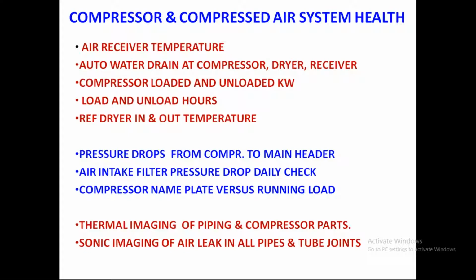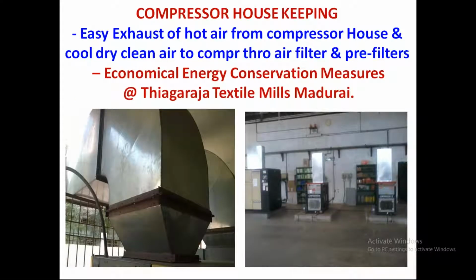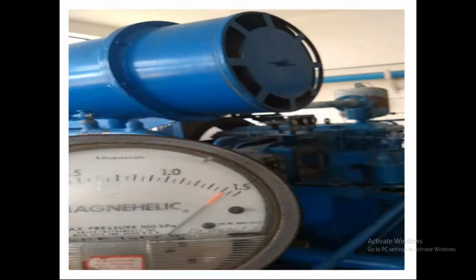What is the reason for heat rejection, as I was telling you before? 70% of the heat is rejected, and that has to be evacuated out of the compressor house. Where you are doing the energy audit, suggest they go for a 3-meter duct and put it on top of the compressor skid. Automatically the hot air is taken to the top, and the surroundings of the compressor are kept cool. Some just-in-time measures have to be done in the industry, in the utility, to improve energy conservation and efficiency measures.